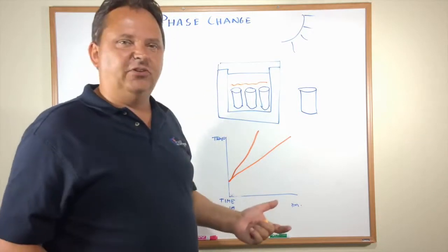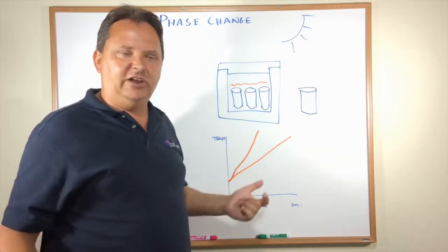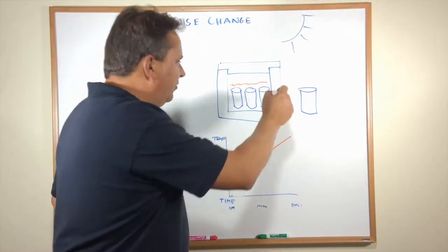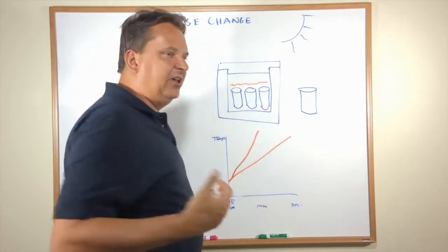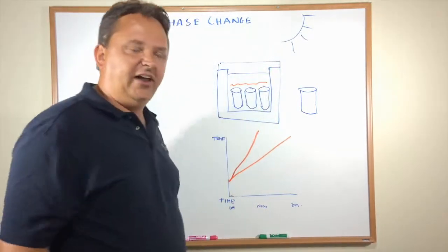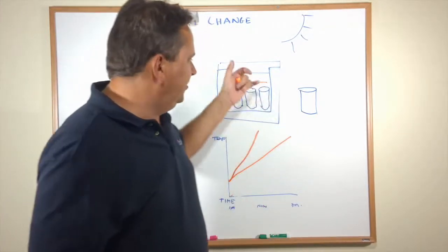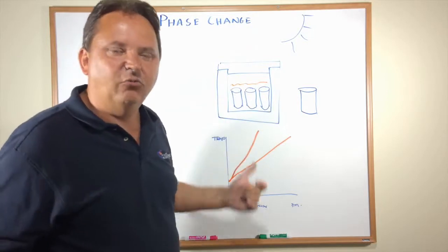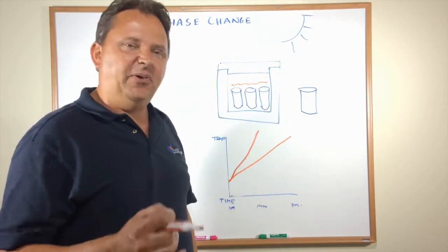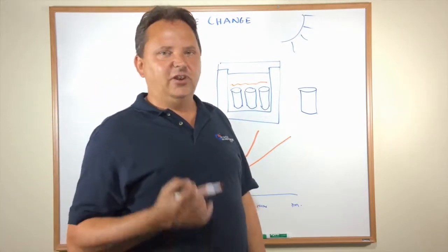With our phase change materials, we set them to temperatures around room temperature, like 73 degrees. So if we have them in our structure, our cooler, when the cooler tries to heat up, they'll begin to melt, cooling the cooler or the house down to 73 degrees. Now, as the house tries to drop in temperature at night, the phase change materials will actually release heat, warming the inside of the house back up to 73 degrees again. So it has this impact of dramatically reducing the temperature swings in the building, something you never could do with insulation.